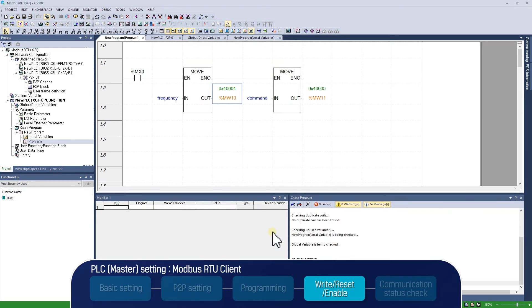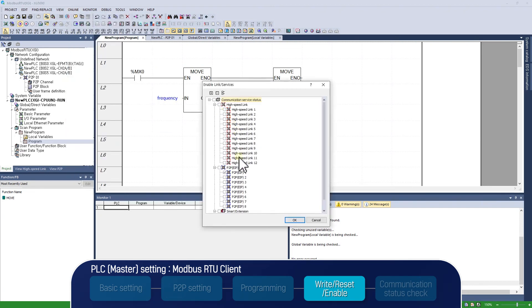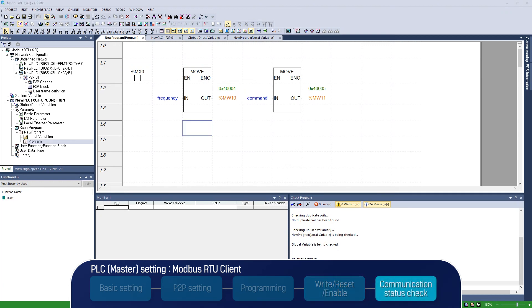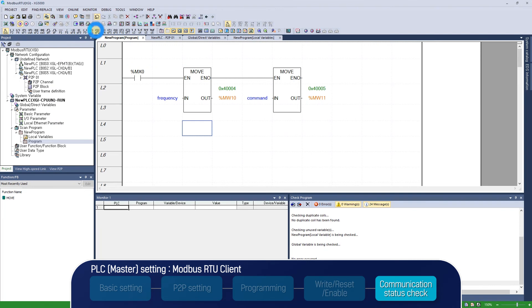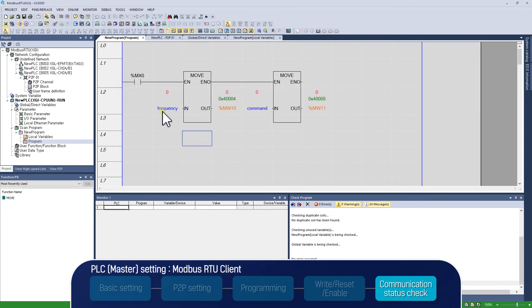Next step is to enable P2P communication. Select Online, Communication Module Setting and Diagnosis, Enable Link Services, and tick off the P2P number to enable. Now XGT client setting is completed. Now let's monitor the communication status. When you change the value of MW10 reference frequency and MW11 run command in PLC, the drive will work with the changed data.